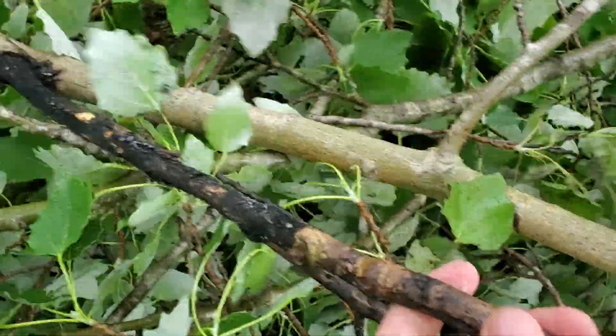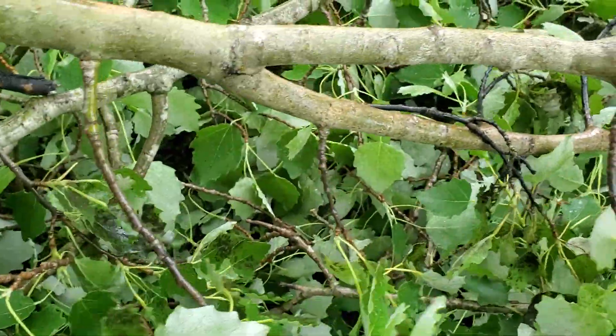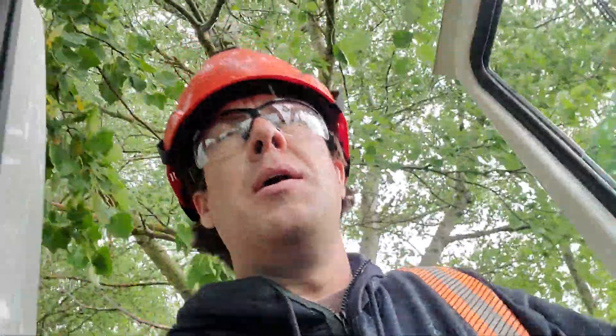All right — one phase and there's the other right there. See the branches that burnt through there. So that's kind of an odd one. I suspect that first branch that we found, which quite obviously had arced, probably happened in the past — it burnt off the main part of the tree, must have activated the reclosing device, which reclosed back in and just hung there, burnt. And this one here — you could smell the charred branch. So this is definitely our guy.